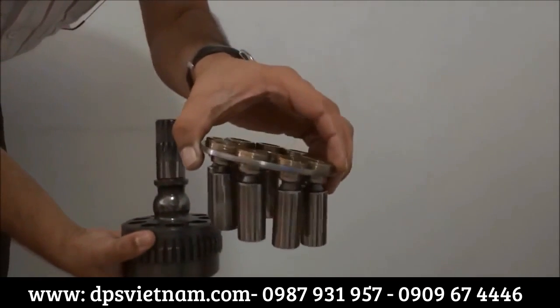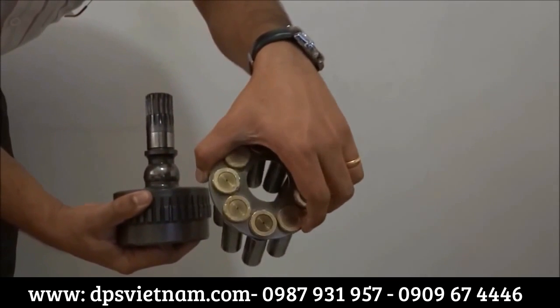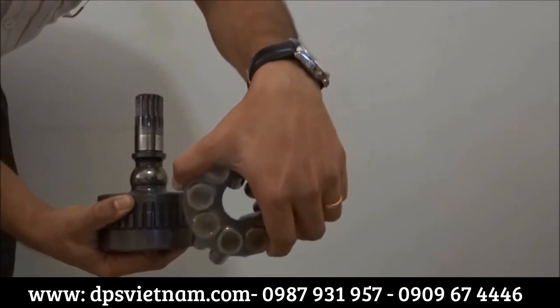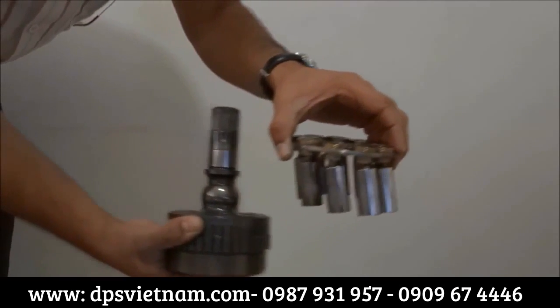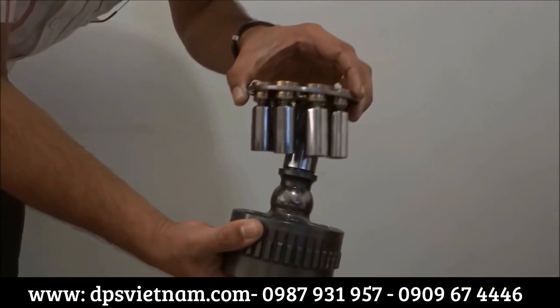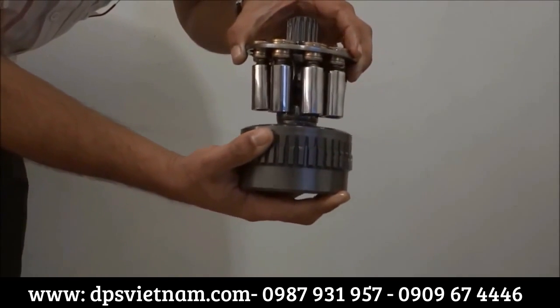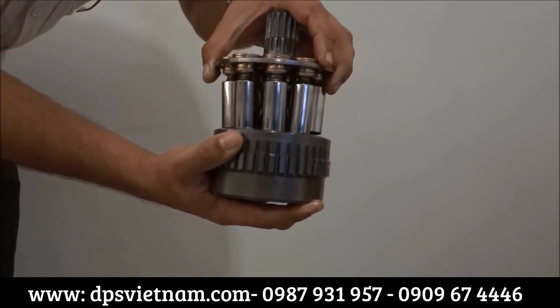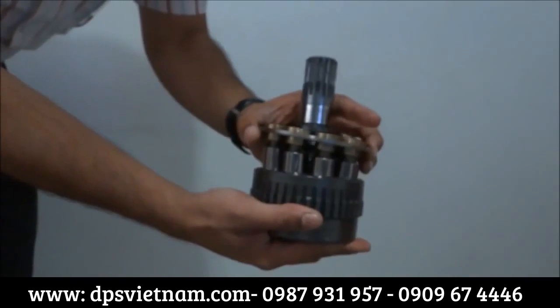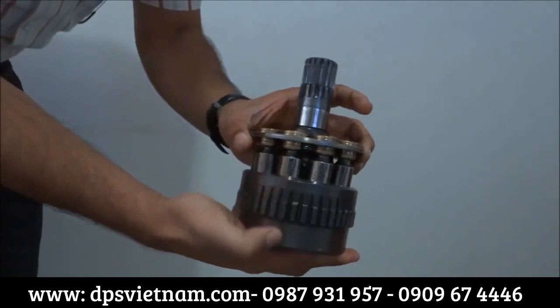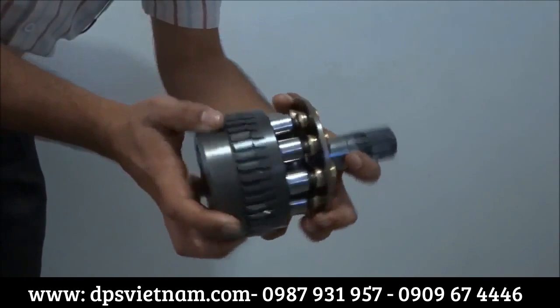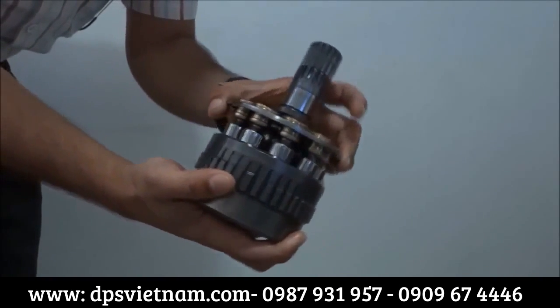Now we'll be putting the pistons back into the cylinder block, and let's see how it can be assembled back. Make sure that once it is removed, it should be put back into the same pot and should not be changed, because they have already mated, and the scoring marks will be like a male-female scoring mark, so it has to be inserted in the same pot. So that's how it looks.